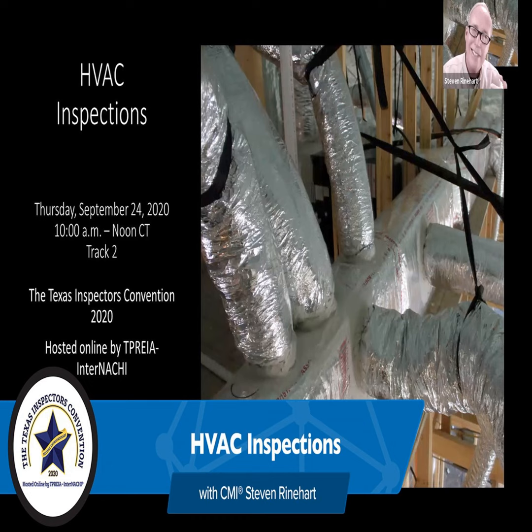You just do your best to ensure, by the standard, that it has that electrical bonding jumper, and don't look exhaustively for it. It should be somewhere obvious, usually where the gas stubs out. If you don't see it, make a note of it. So if I've got gas, even if it's a portable LP tank that just does the fireplace, it's got a metal gas pipe, I'm looking for that bonding.